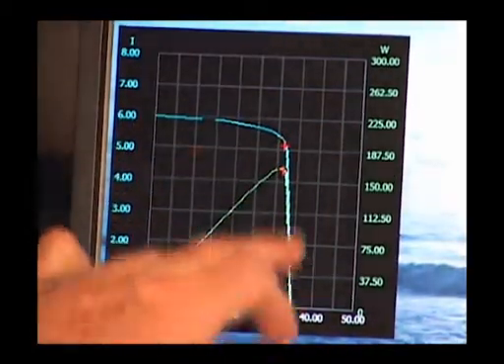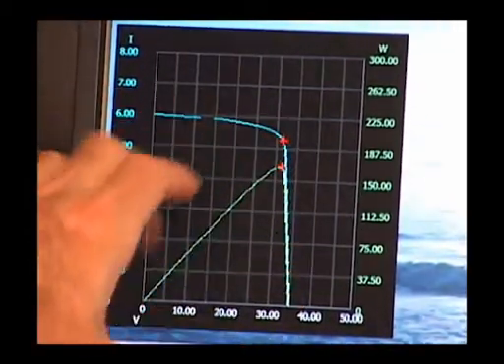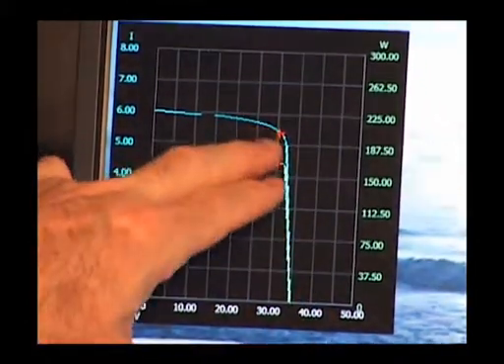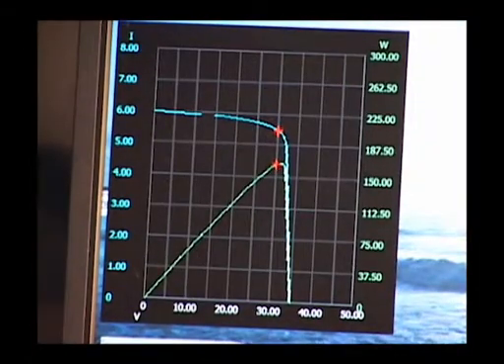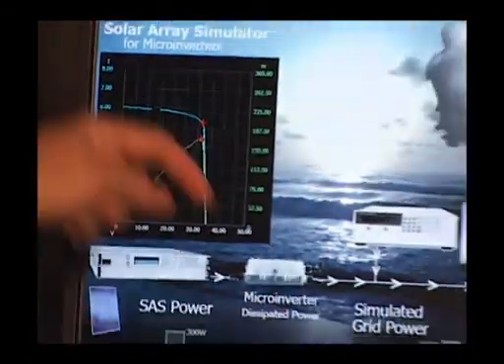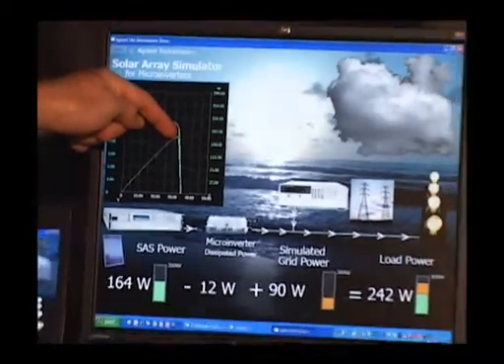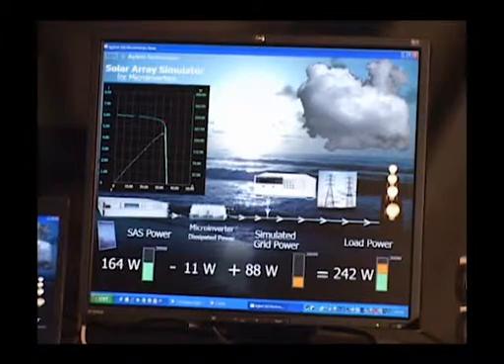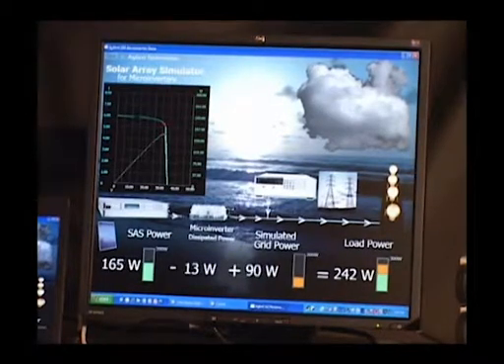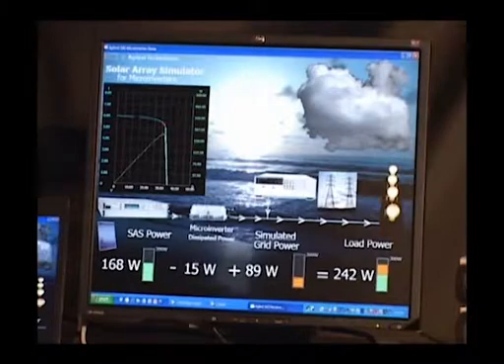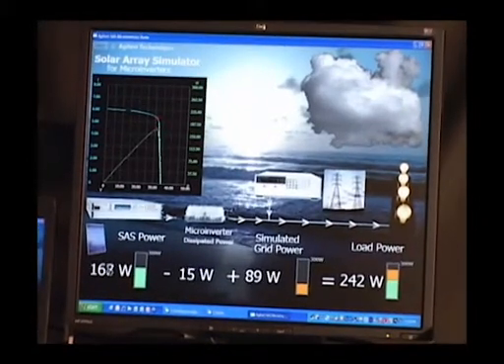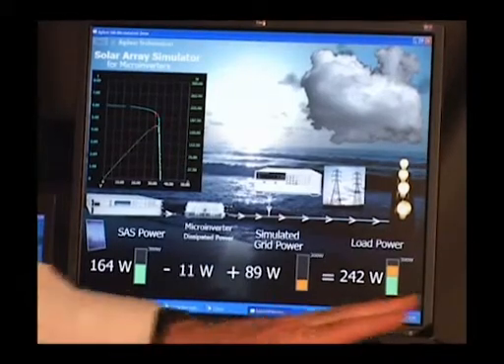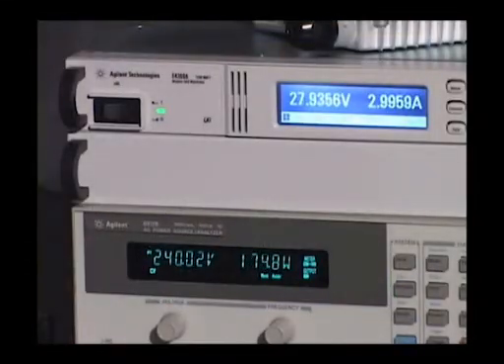At this particular point in the IV curve, the red crosshairs are showing the present operating point on the SAS. You can see that it's operating right at the knee of the power curve and that's the maximum power point. That's actually the job of these microinverters. The job of the microinverter is to harvest as much power as possible from a real solar panel that would be mounted on your roof. In this case it's harvesting that power from our solar array simulator.